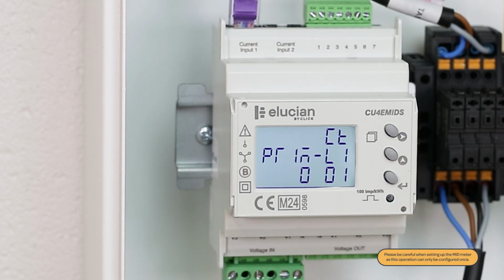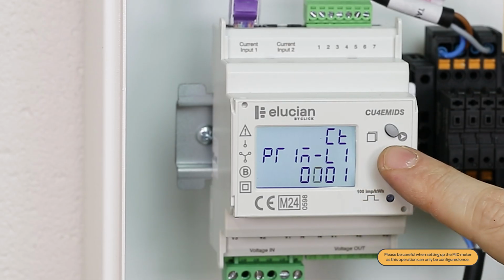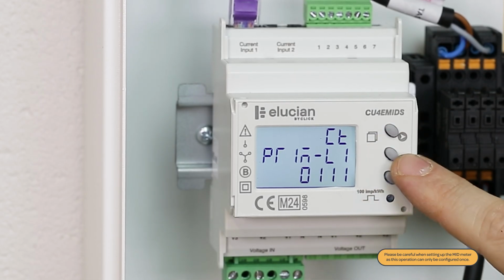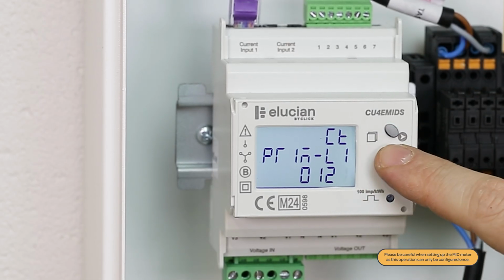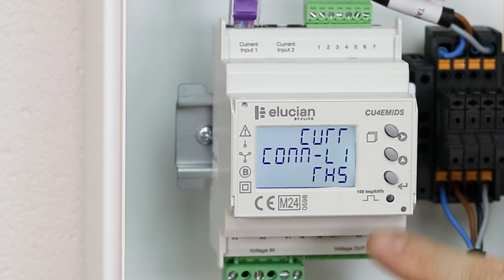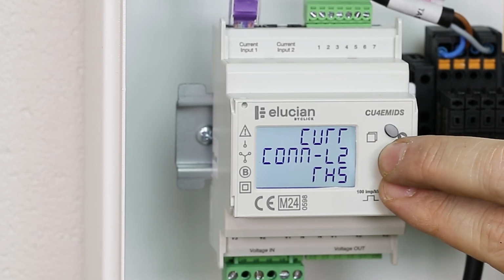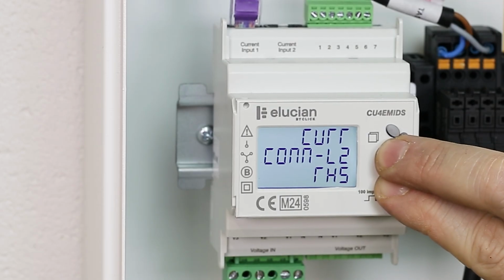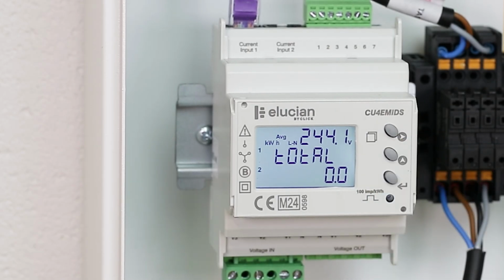Here we want the current transformer ratio to be 125, which can be inputted into the energy meter display by switching between the top and middle buttons. Press the lower button to confirm the ratio. Press and hold the lower two buttons together for 3 seconds to return to the main screen and complete the setup.